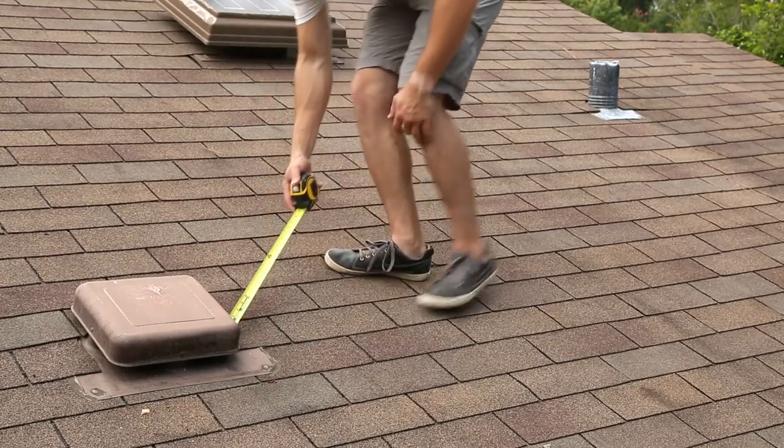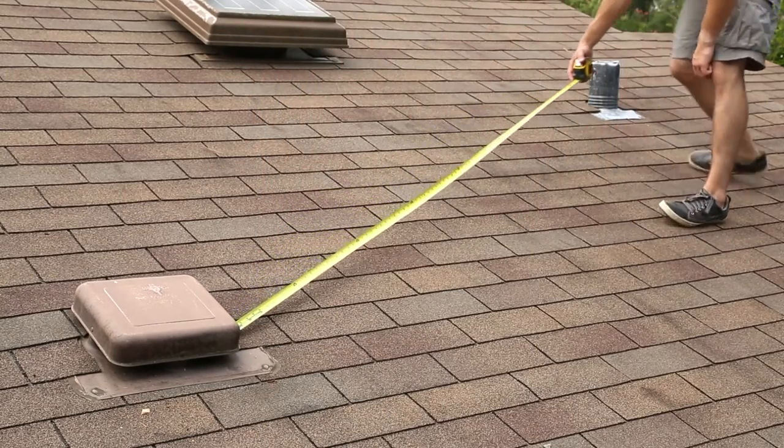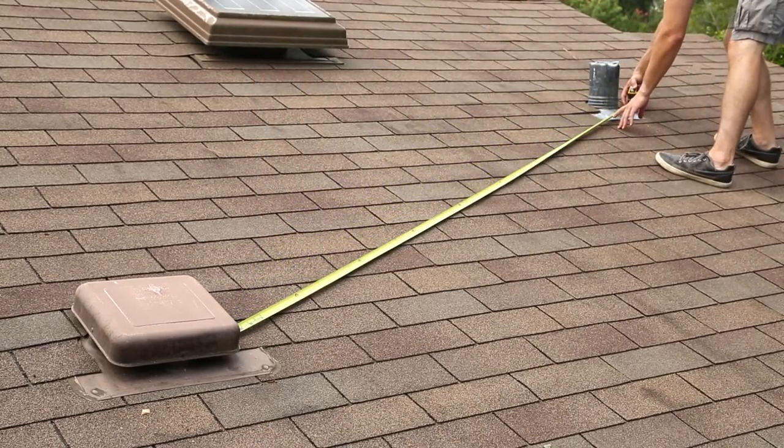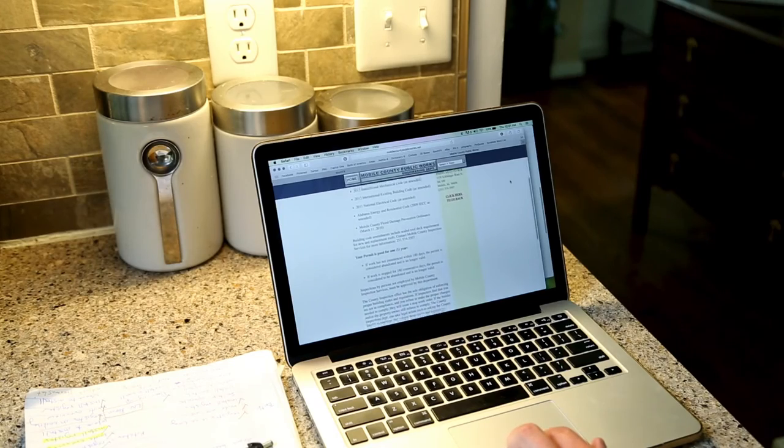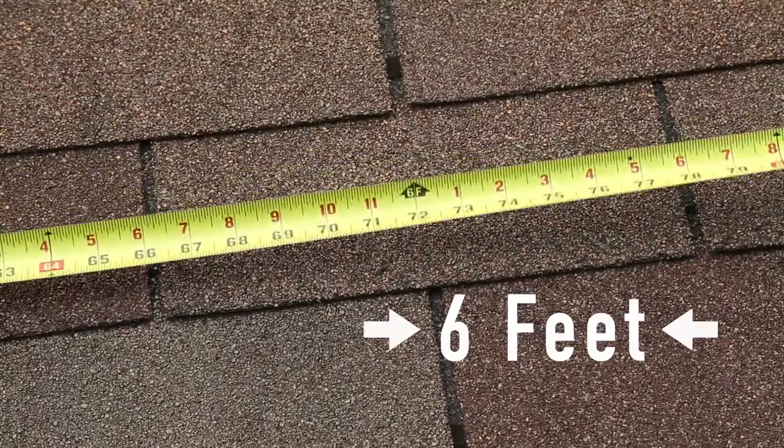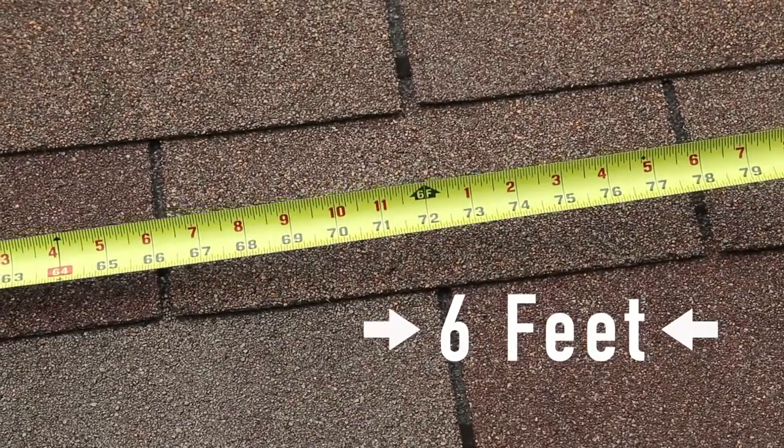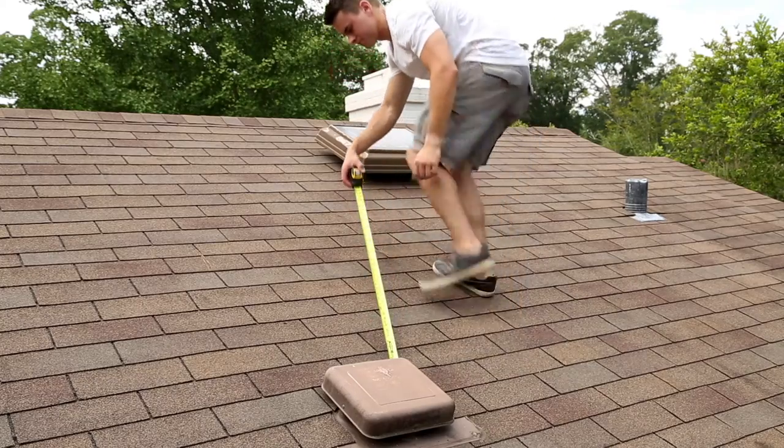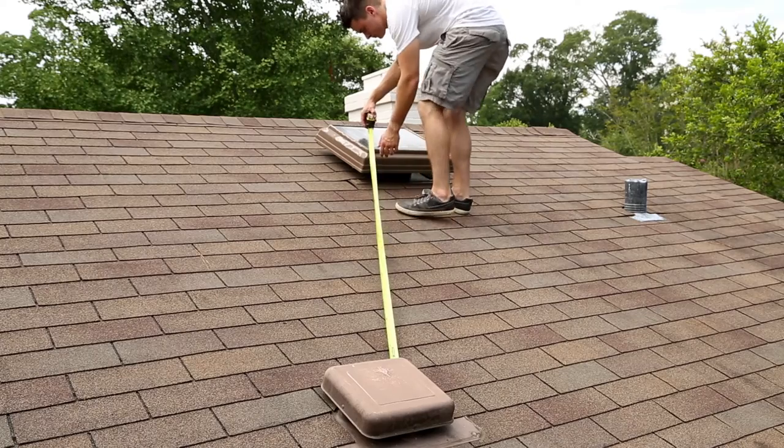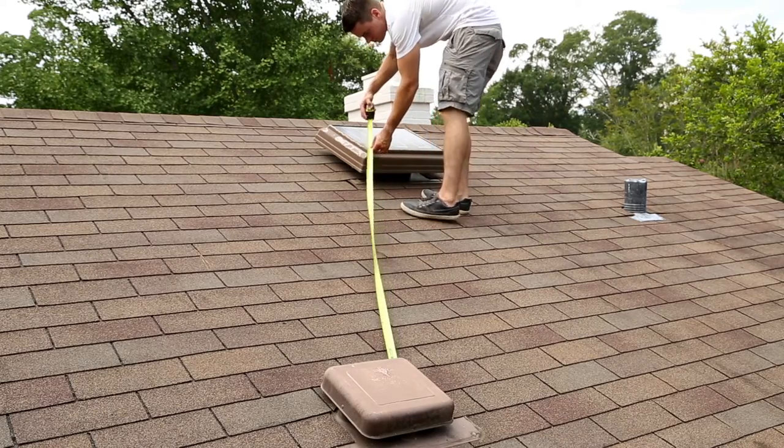Now it is time to install the stale air exhaust hood and fresh air distribution hood. Consult applicable building codes to determine hood placement. To avoid contamination, ensure the intake hood is at least six feet from any exhaust. You also want at least six feet between the exhaust and distribution hoods to avoid contamination.